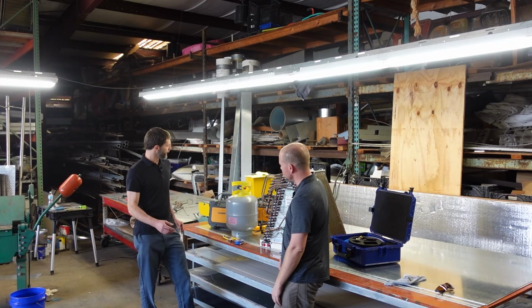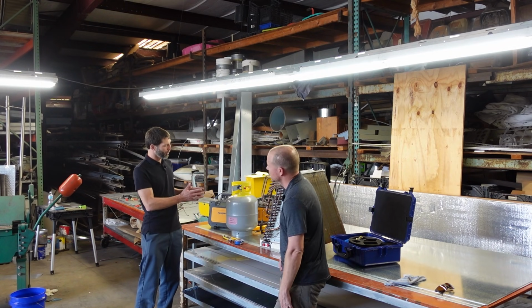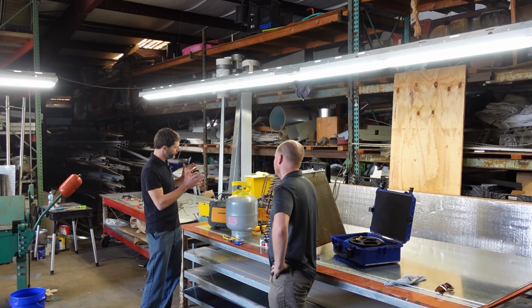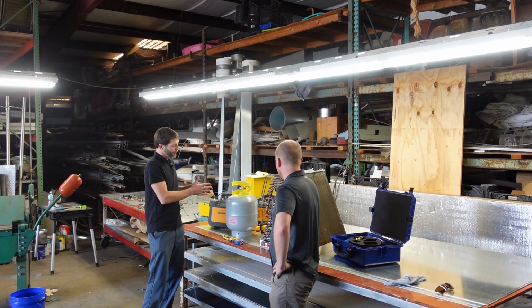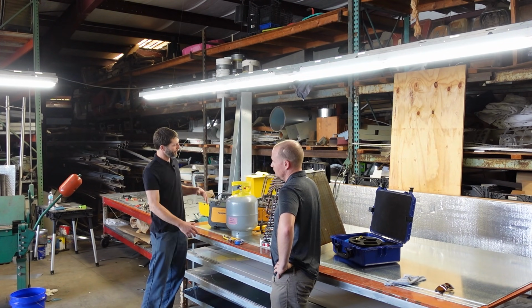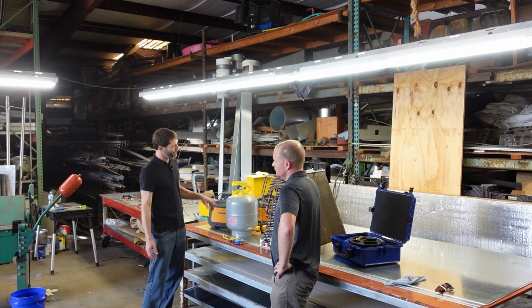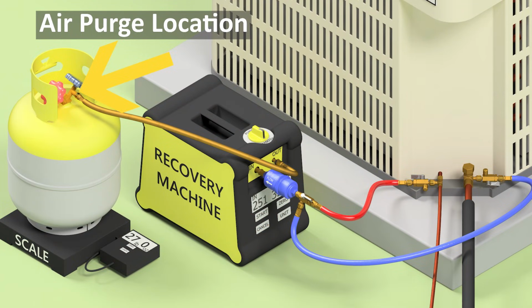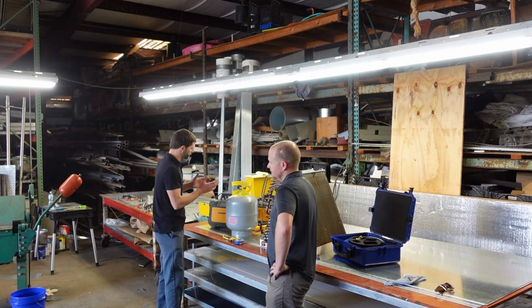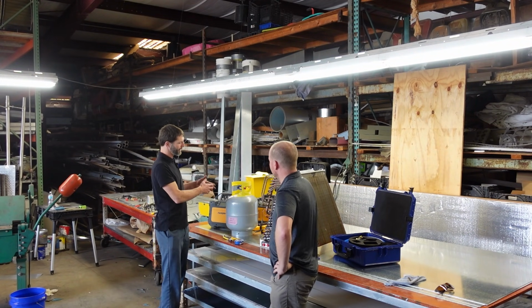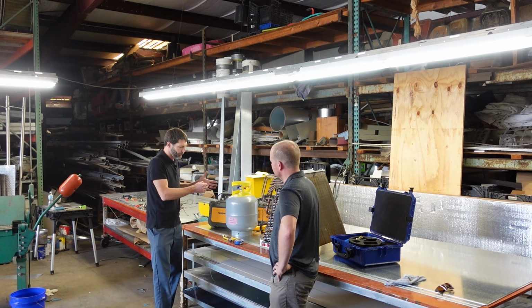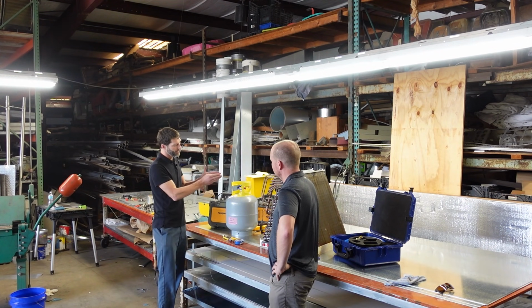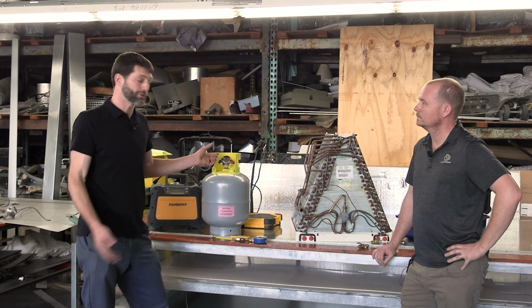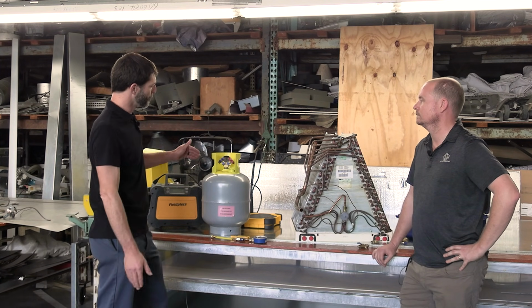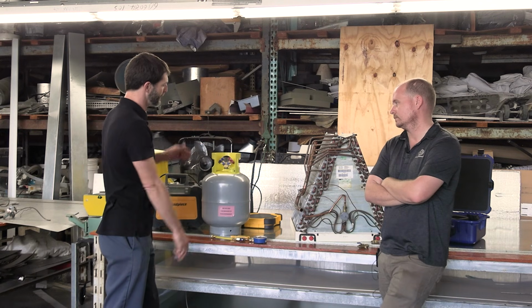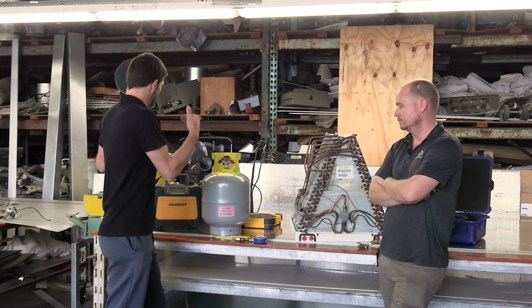Now, when you do hook up your hoses, you want to purge all of the air out of the hoses before you start your recovery. Sometimes people do a vacuum on that, but if you're just purging the air out, you can do it over at your recovery tank. Basically you have your hoses going to your recovery machine, and from your recovery machine a semi-short but still large hose going to your recovery tank. At your recovery tank, that's where you purge the air out from the hoses before you close your hose back down onto the fitting and open up your recovery tank to get ready for the recovery to start.